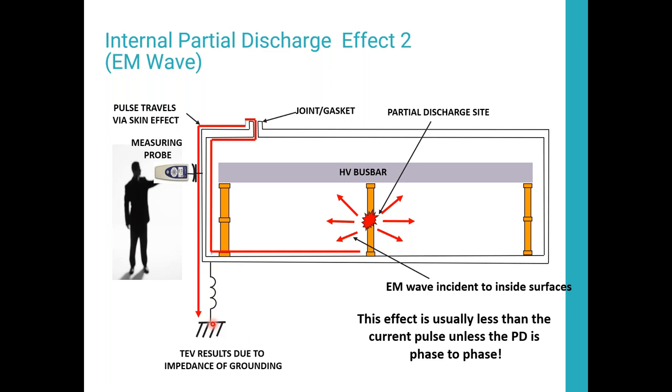Now, if you remember, the VLF test has a capacitive coupler that attaches to the equipment or to the cable. That's basically what they're doing: capacitive coupling to the shield and measuring these current pulses as a voltage on the instrument. It's a form of TEV. But that's what we do in TEV measurements, looking for failures in solid insulators in your switchgear.